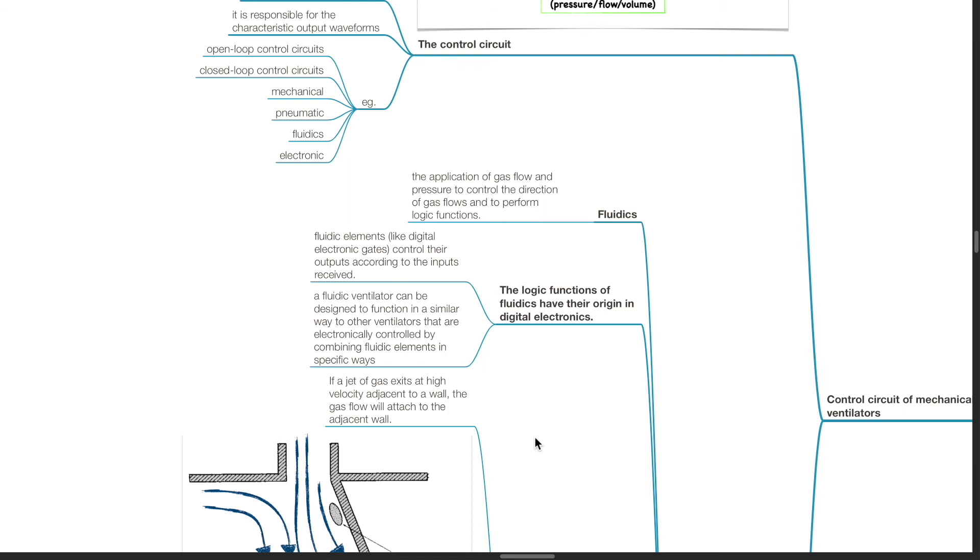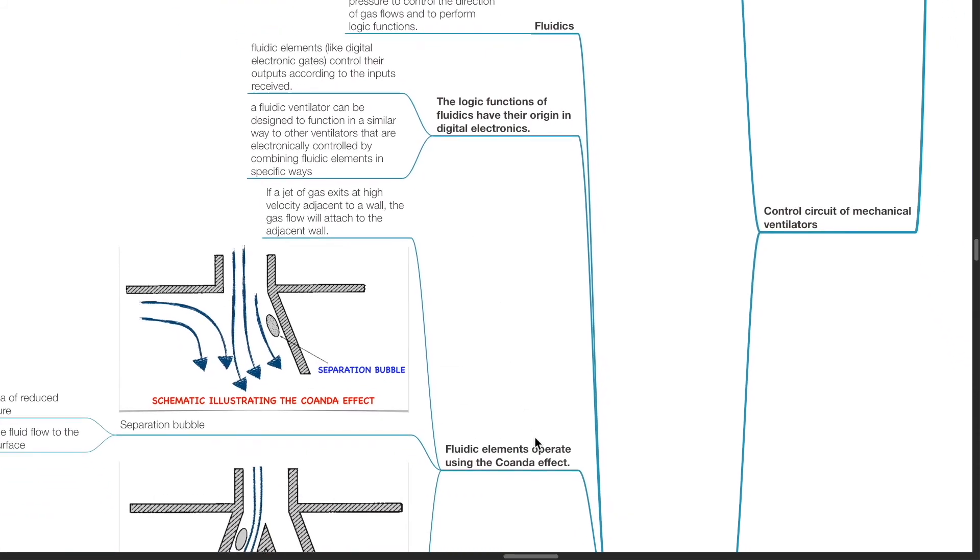Fluidic elements like digital electronic gates control their outputs according to the inputs received. A fluidic ventilator can be designed to function in a similar way to other ventilators that are electronically controlled by combining fluidic elements in specific ways.